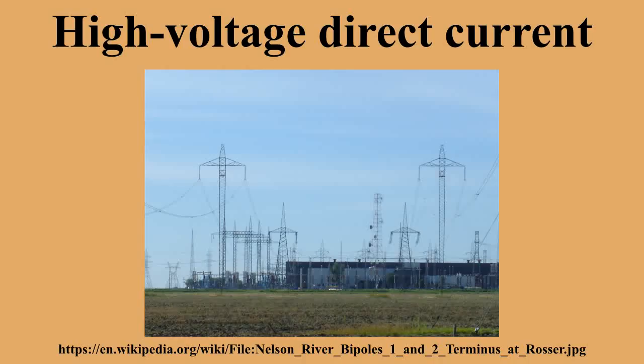Power transmission and stabilization between unsynchronized AC networks, with the extreme example being an ability to transfer power between countries that use AC at different frequencies. Since such transfer can occur in either direction, it increases the stability of both networks by allowing them to draw on each other in emergencies and failures, stabilizing a predominantly AC power grid without increasing fault levels.